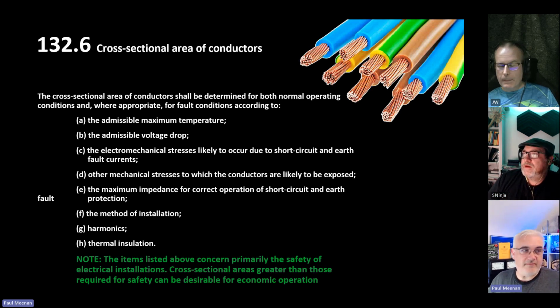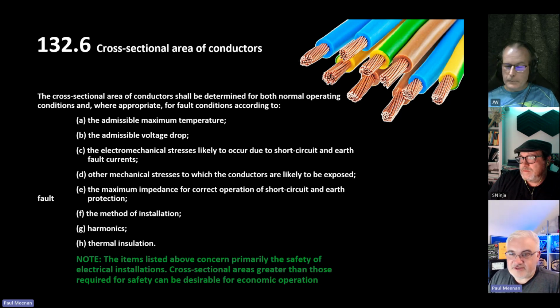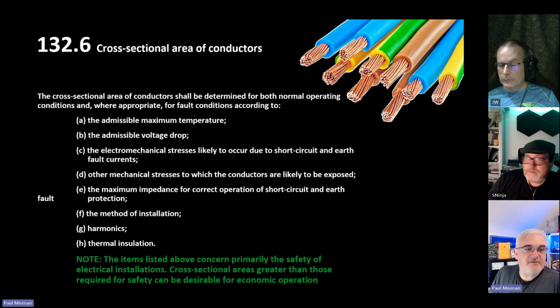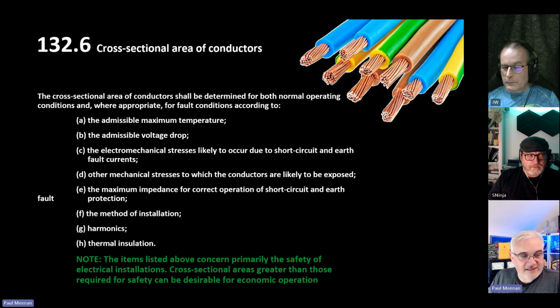Let's get into part one. The first regulation isn't a change, it's an addition of a note - section 132.6. Part one's my favourite bit, fundamental principles and all that. The cross-sectional area for conductors shall be determined for both normal conditions and where appropriate fault - that's fine, that's why we do adiabatics and all that. But there's a note at the bottom saying the items listed above concern primarily the safety of electrical installations, and cross-sectional areas greater than those required for safety can be desirable for economic operation.